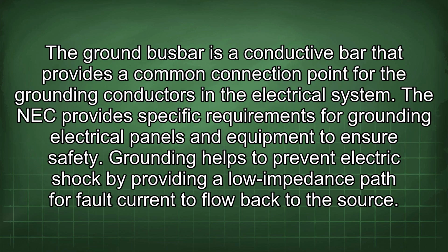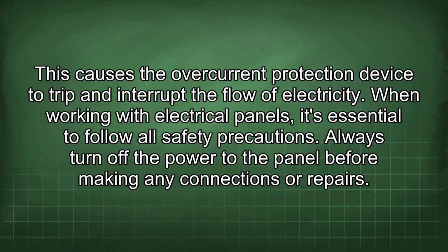The ground bus bar is a conductive bar that provides a common connection point for the grounding conductors in the electrical system. The NEC provides specific requirements for grounding electrical panels and equipment to ensure safety. Grounding helps to prevent electric shock by providing a low impedance path for fault current to flow back to the source. This causes the overcurrent protection device to trip and interrupt the flow of electricity.